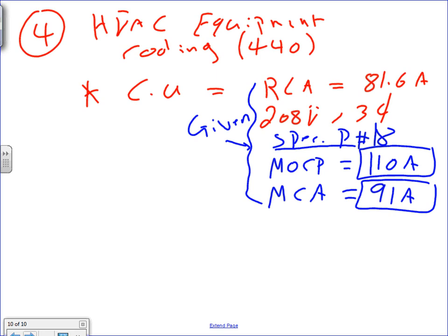And if you guys look at the bottom of the sheet, it says or HACR circuit breaker. Because I'm using circuit breakers, I can't use a fuse in a circuit breaker panel. Where are you gonna fit it? It doesn't fit. So at the bottom it says you can put HACR, the same size. Okay, very easy. This is very easy, guys.